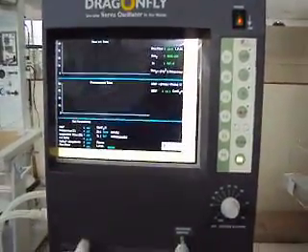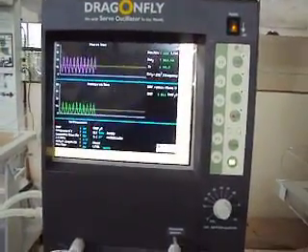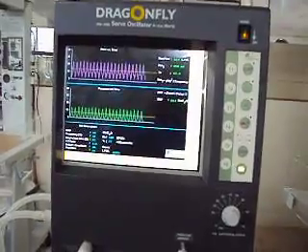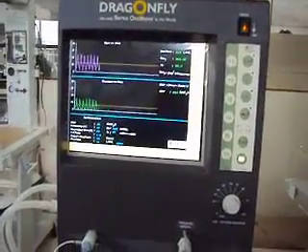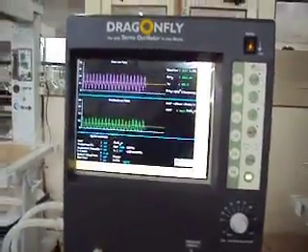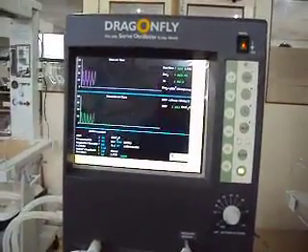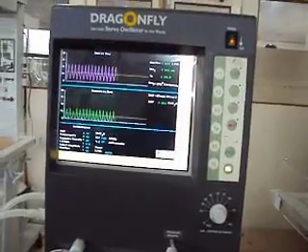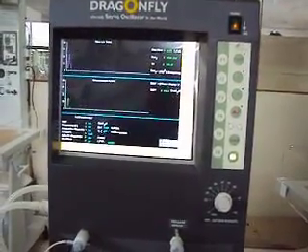This, my friends, is the HFOV — the Dragonfly — the world's only true servo-controlled high-frequency oscillatory ventilator that can be used to treat patients from 600 grams to 20 kilos. A couple of our doctors have also successfully treated patients weighing as low as 475 grams and as high as 26 kilos. The machine is sturdy, has proved its worth, is CE and ISO 13485 certified, and has passed every possible test you could put it through. I look forward to receiving your inquiries, queries, doubts, suggestions, and feedback.